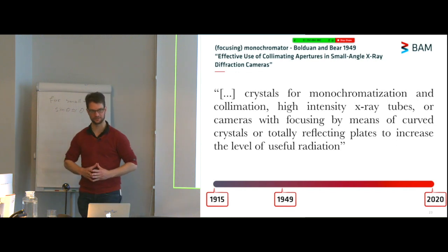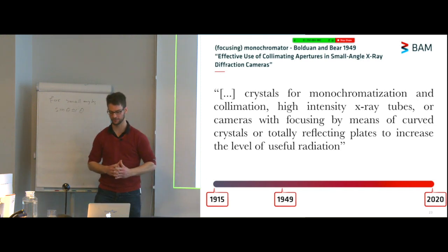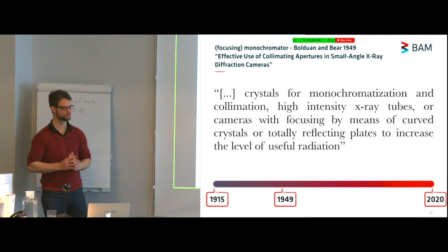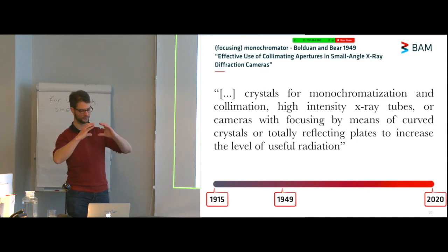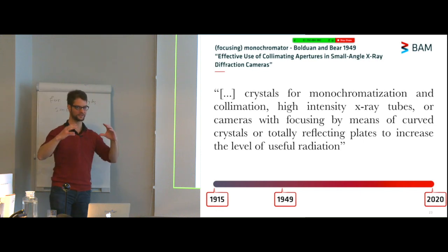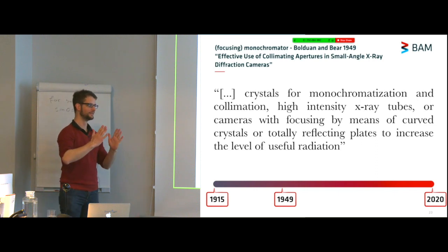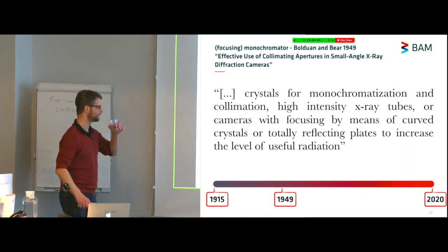This is not self-explanatory as I found out, in particular the focusing by means of curved crystals. I came across an instrument where they wanted to focus the X-rays and what they had done was taken a block of silicon and cut out a parabolic shape out of that block. This does nothing for your focusing because the crystalline lattice is actually exactly the same. So the X-rays don't bend, they're not reflected to different angles, they're reflected to exactly the same angle. Apparently not all lessons from the past are remembered.